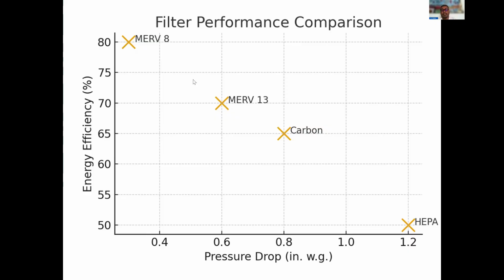Whereas in some cases, like I said, they're using HEPA for clean room. Well, they naturally have a higher pressure drop. And because of that, your fan will have to work harder. Nobody's saying only use MERV 8s, and nobody's saying never use HEPAs. What we are saying is this is something that you should consider and at least understand how it would fall in range of how you're going to affect your fan efficiency.